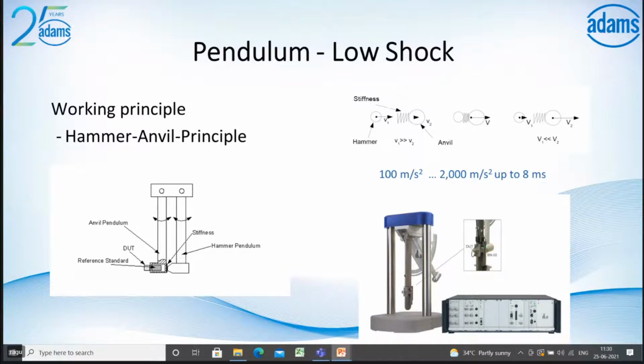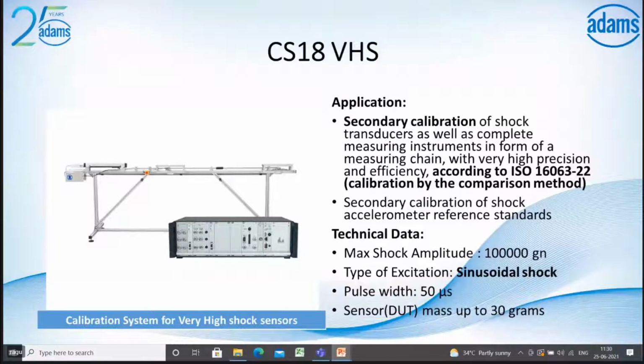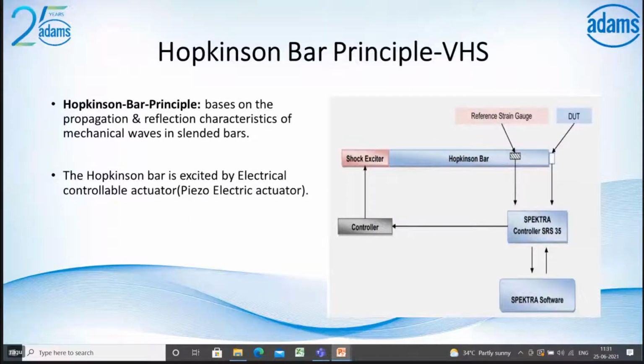CS18 VHS, it's a secondary calibration of shock transducers. It's a very high shock system according to the standard ISO 16063 by comparison method. The maximum amplitude you can go up to is 1 lakh G, and its excitation is a sinusoidal shock. The pulse width, half sine and full sine, is 50 microseconds. The working principle is the Hopkinson bar principle, which is patented to Spektra. The principle is the propagation and reflection of mechanical waves in a slender bar, which generates the shock, and the bar is excited by the piezoelectric actuator, that's the shock exciter.